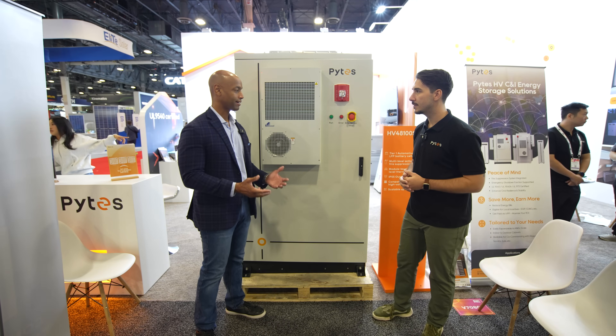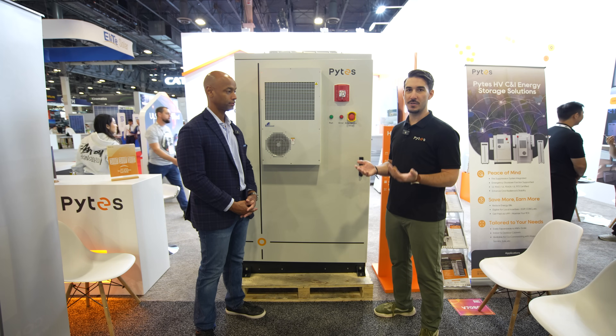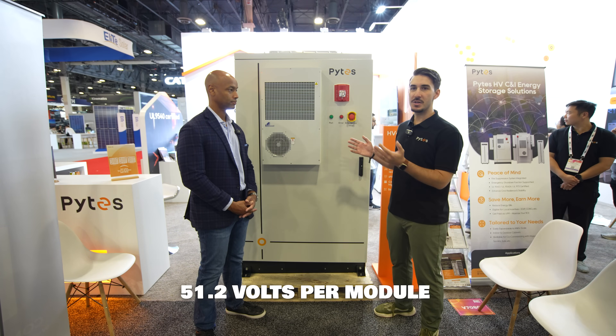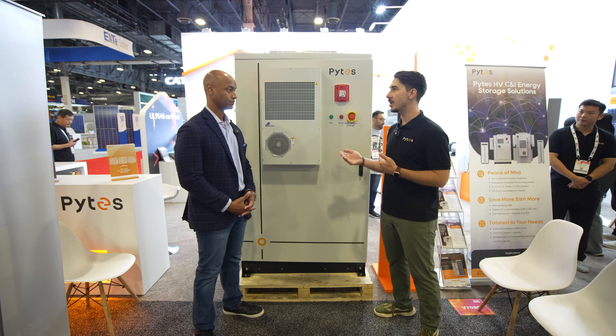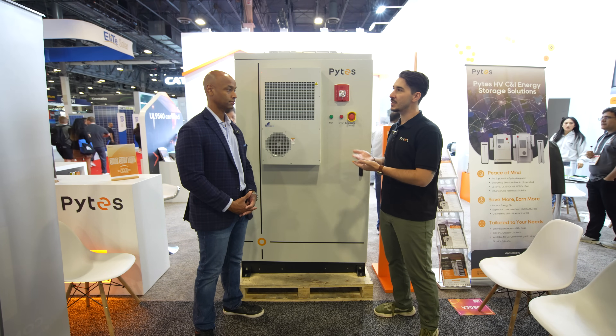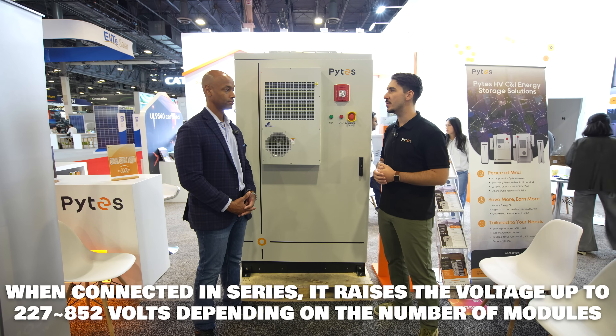When you talk about a high voltage solution, what does that typically mean in terms of operating range? Most of what Pytes has developed up to this point has been in the residential space — 51.2 volt nominal solutions. We're using very similar modules inside this cabinet; all that's really changing is the method of connection. Instead of connecting the batteries in parallel to maintain that low voltage on the DC bus, we're connecting them in series. That raises the voltage on the DC bus, achieving anywhere between 250 to maybe up to 850, close to 950 volts for the batteries.